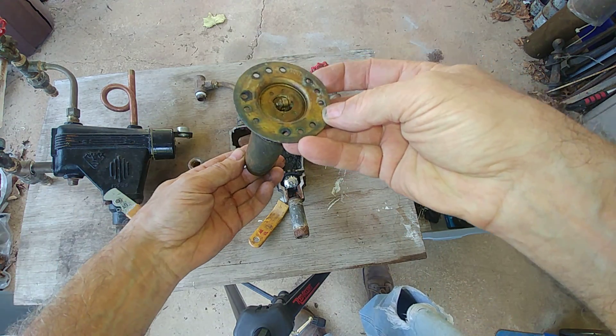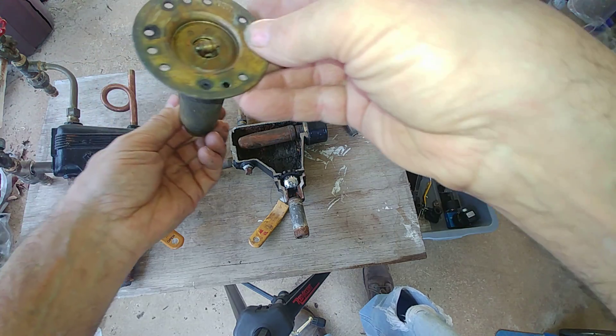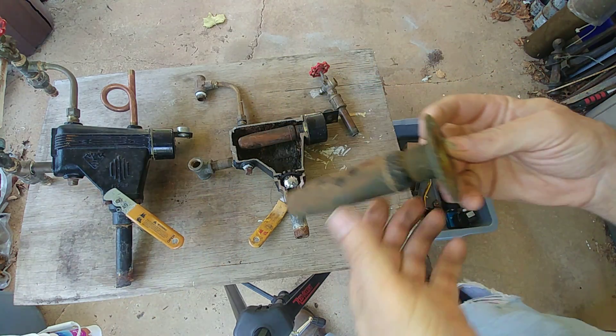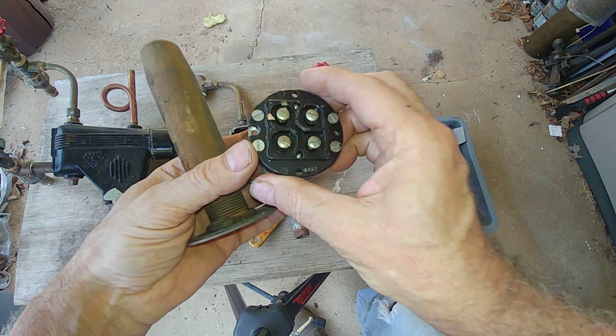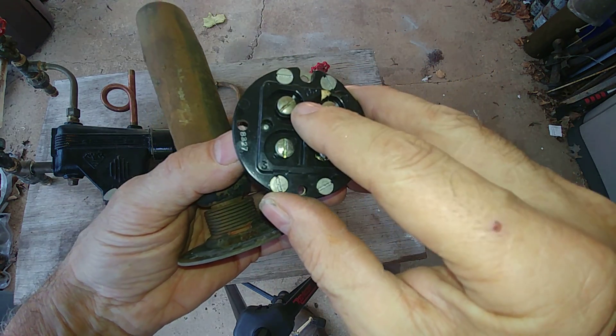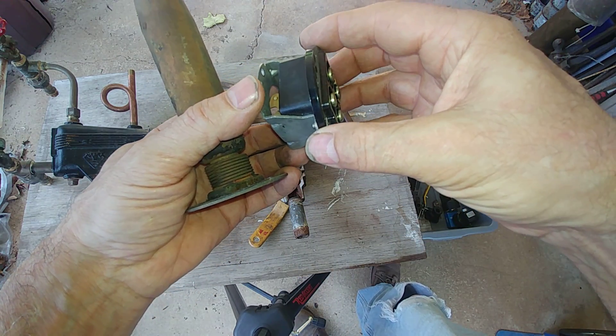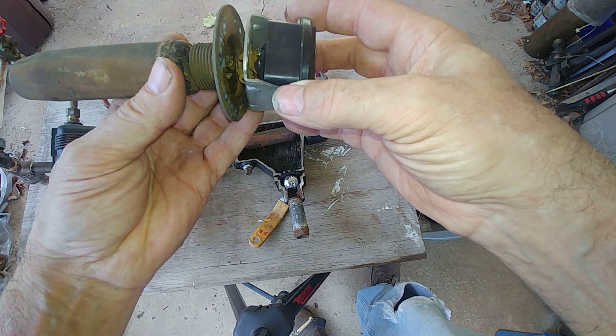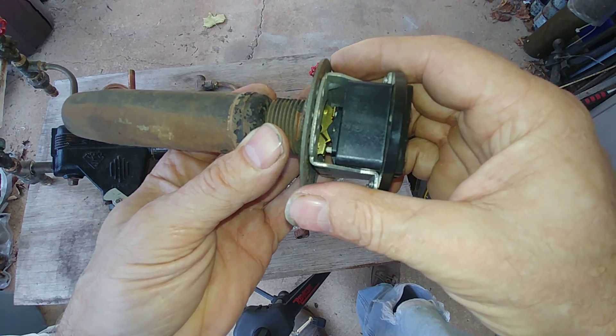Here's the float that's been disconnected. There's a bellows here — a siphon — and this floats and moves up and down, operating this cam. This is the switch in the back, and this is the heart of the show — a highly engineered component. The switch is replaceable, fairly expensive, and we'll get into that. It hooks to there like so.